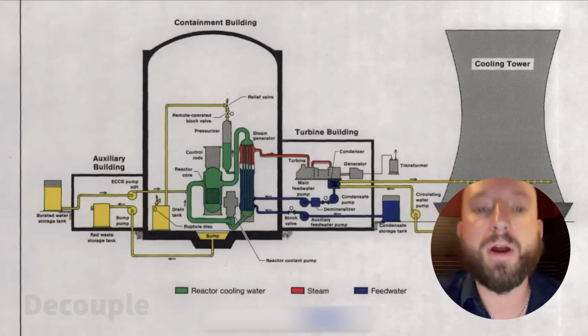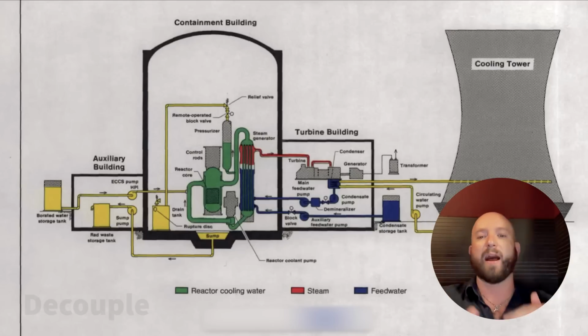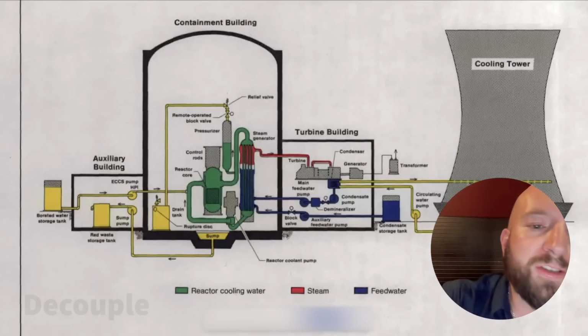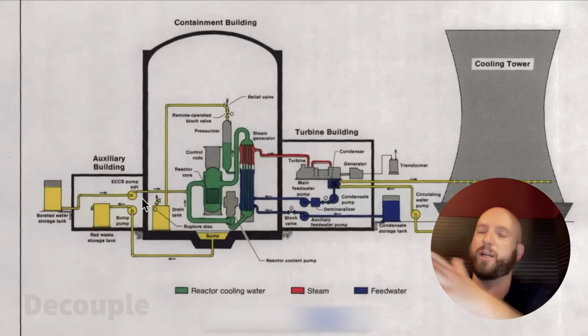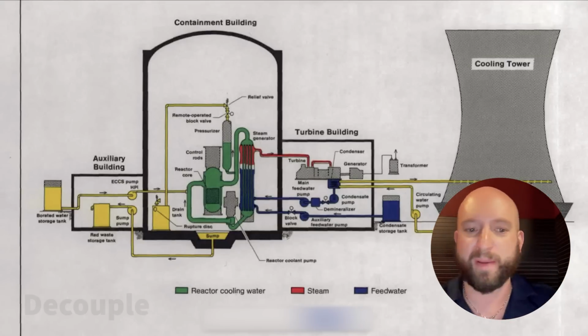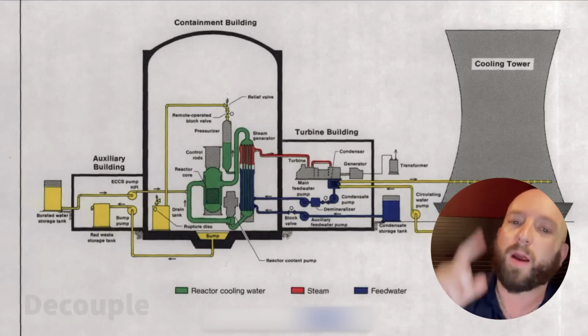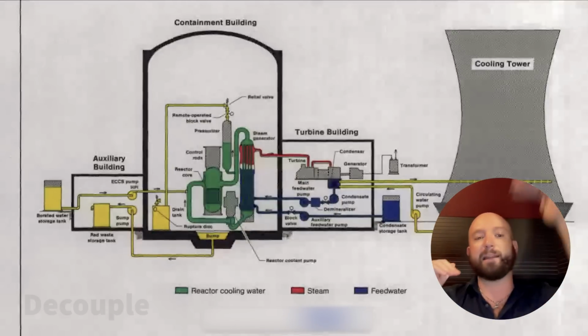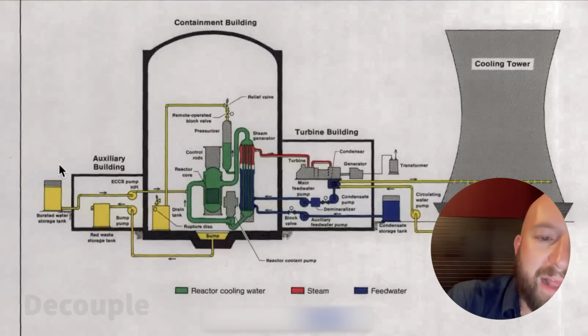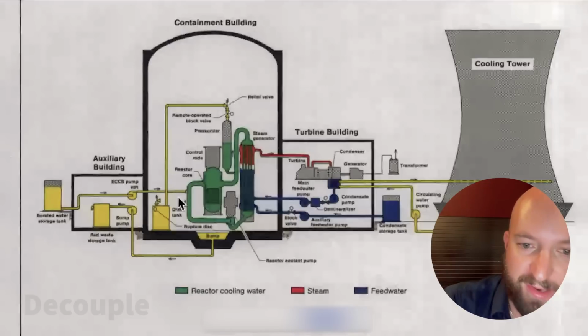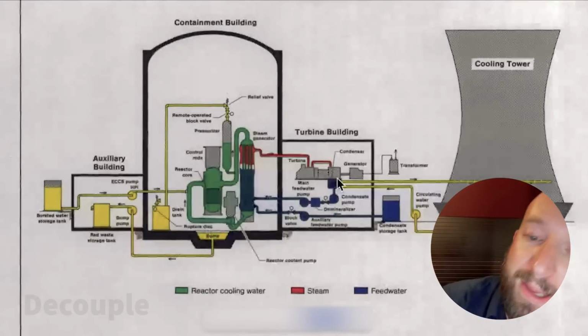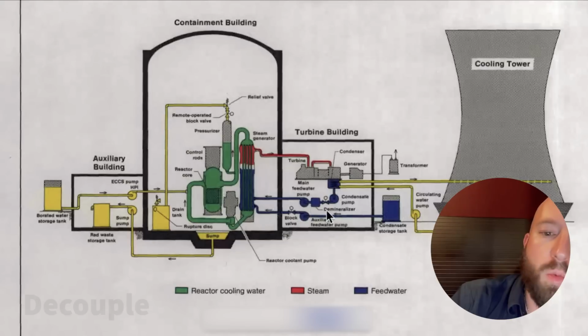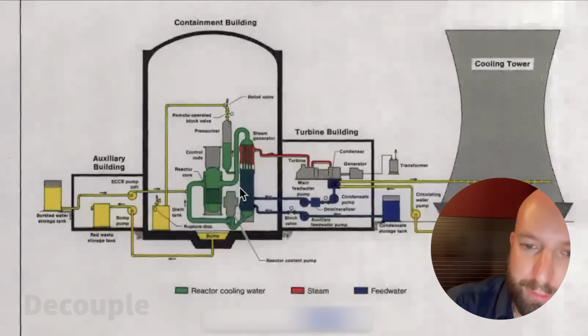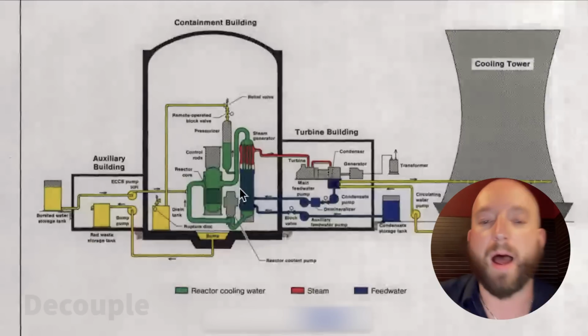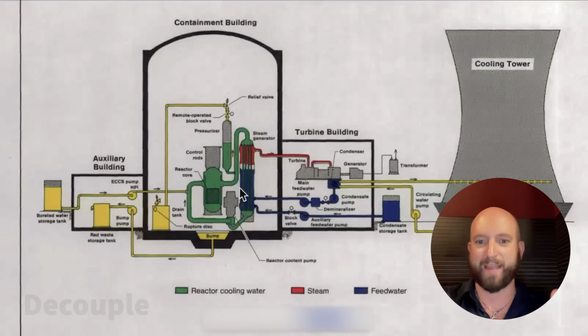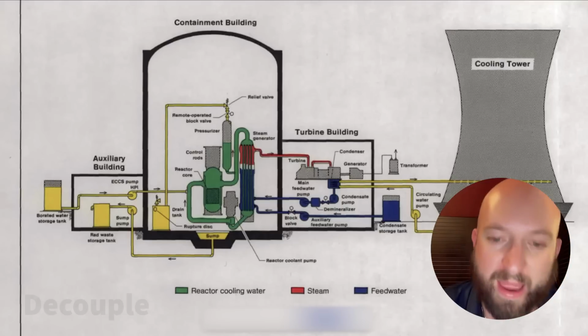No, it is not. The emergency core cooling system, which we're about to get to, is not the auxiliary feed water system. The emergency core cooling system consists of two trains of high pressure injection, or HPI, sometimes called HPSI, high pressure safety injection, and LPI, low pressure safety injection, which directly inject water into the reactor coolant system, so into that primary system. The auxiliary feed water system is directing water into the secondary system on the other side of the steam generators. Right? So they are two very distinct systems, and we're about to get into where that distinction becomes critical.